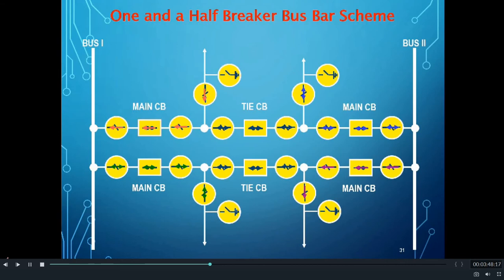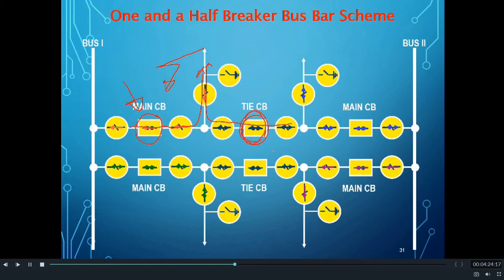Now let us see how LBB operates in the one and a half breaker scheme. Suppose there is a fault in one of the feeders. The fault current will flow from the TIE CB side and the main CB side. So as to clear the fault, the TIE CB and the main CB will trip normally. But if because of some problem the main CB does not operate, then because of the operation of the TIE CB, the fault current which was earlier flowing from the TIE CB side will stop flowing. However, the current which was flowing from the main CB side will continue to flow.